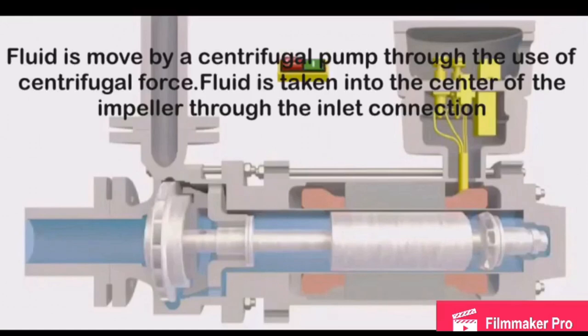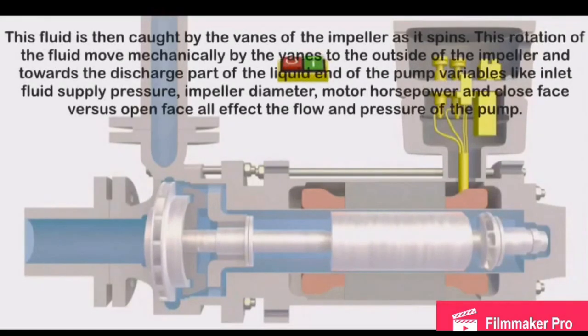For the working principle of canned motor pump, the fluid is moved by a centrifugal pump through the use of centrifugal force. Fluid is taken into the center of the impeller through the inlet connection. This fluid is then caught by the vanes of the impeller as it spins. This rotation of the fluid is moved mechanically by the vanes to the outside of the impeller and towards the discharge part of the liquid end of the pump.